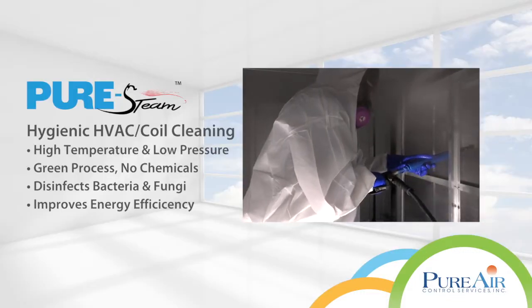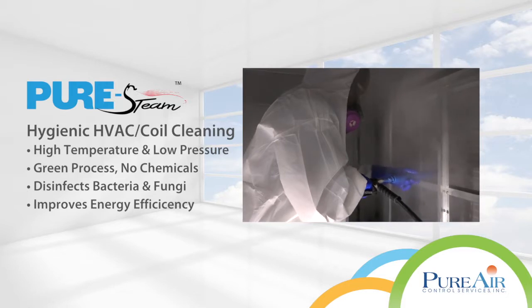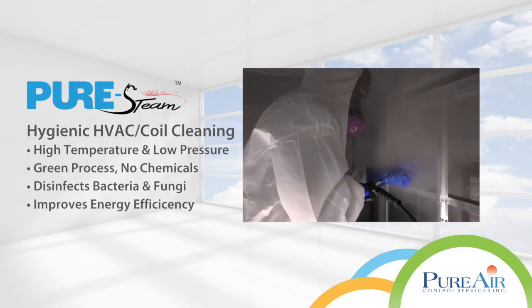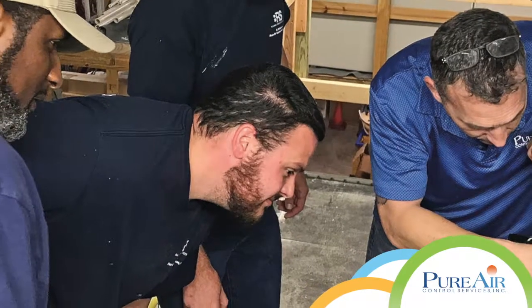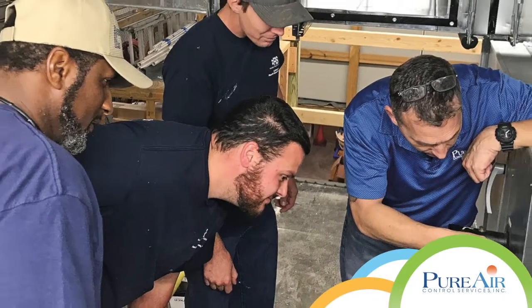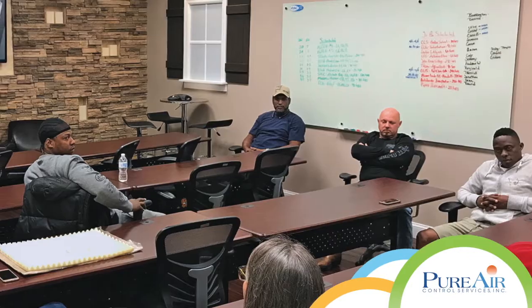Inside of the air handling units, our technicians use a proprietary high-temperature, low-pressure steam process to sanitize the coils and interior components. Axial fans and wet-dry vacs are used to maintain water control and disperse the steam. Our team goes through a rigorous training process to learn these HVAC cleaning procedures, as well as all applicable OSHA regulations.